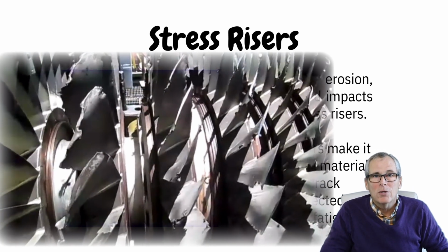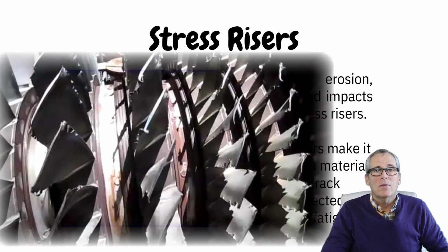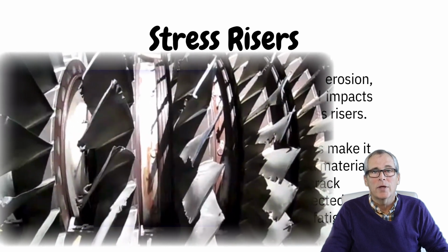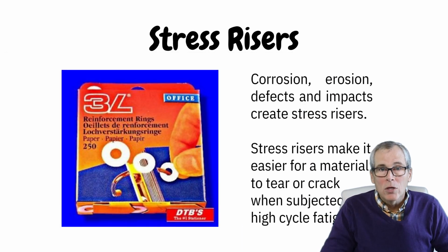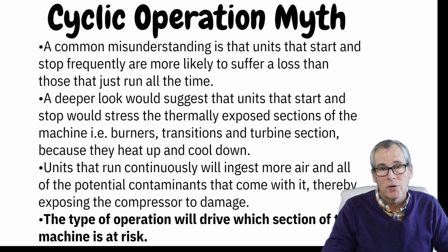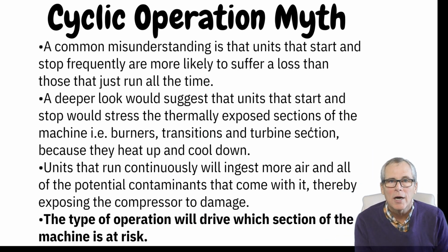If a stress riser develops in a gas turbine compressor blade or turbine blade, then it's not desirable. And what can happen is that much lower stresses than we anticipated are going to be able to cause the blade to liberate or break. We can look for stress risers through inspections, through borescopes, through eddy current, through dental molds. There's ways to detect stress risers, and a conscientious maintenance program is the best defense against blade liberation from stress risers.